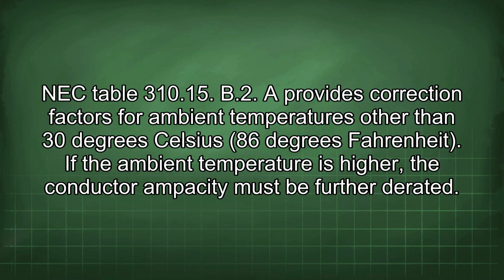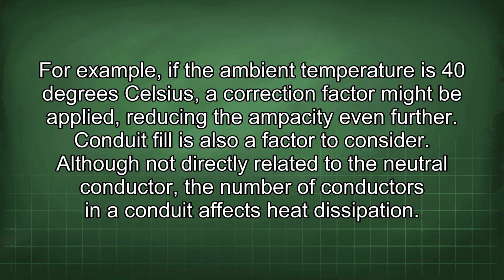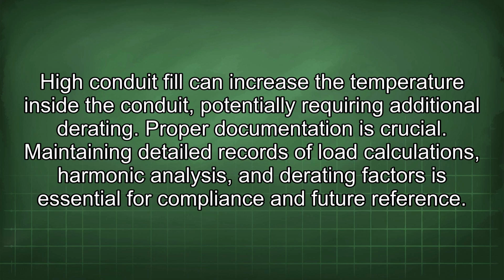NEC Table 310.15(B)(2) provides correction factors for ambient temperatures other than 30 degrees Celsius, 86 degrees Fahrenheit. If the ambient temperature is higher, the conductor ampacity must be further derated. For example, if the ambient temperature is 40 degrees Celsius, a correction factor might be applied, reducing the ampacity even further. Conduit fill is also a factor to consider. Although not directly related to the neutral conductor, the number of conductors in a conduit affects heat dissipation. High conduit fill can increase the temperature inside the conduit, potentially requiring additional derating.